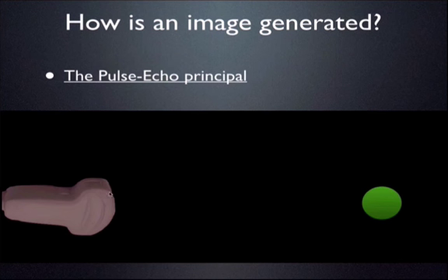When an electrical impulse comes along and causes those crystals to vibrate, this is called the piezoelectric effect, and that is the reason the crystals arranged in the face of the probe are called piezoelectric crystals. The piezoelectric effect is the conversion of electrical energy into a mechanical force, mechanical force being something that causes compression or bending on a structure. In this case, it's the medium that surrounds the probe. So then you have your sound wave that is generated, and it goes out and bounces off of all of the surrounding structures, and you get a return signal in the form of the echo.